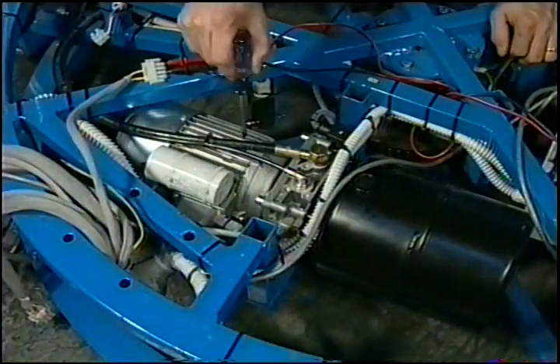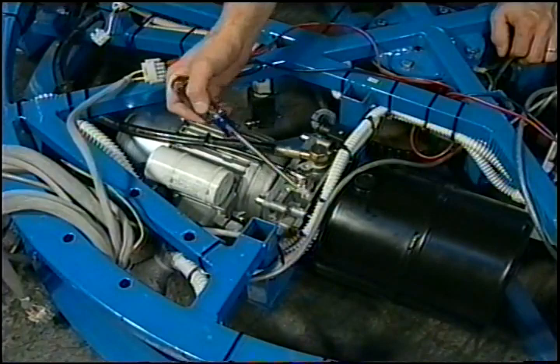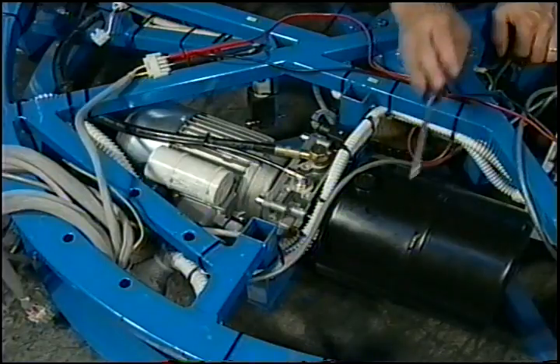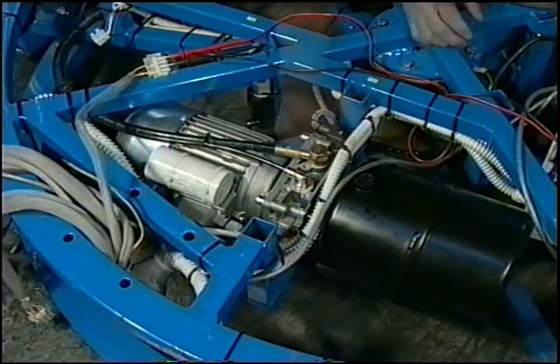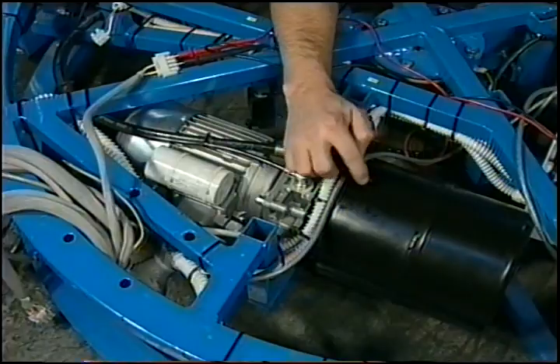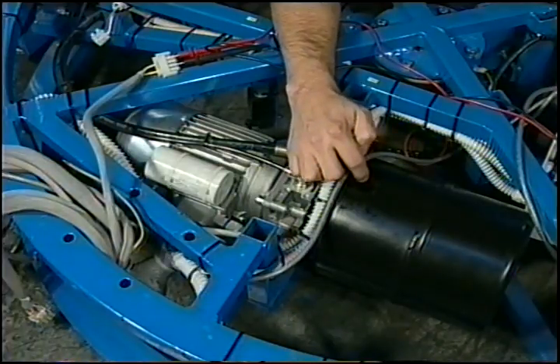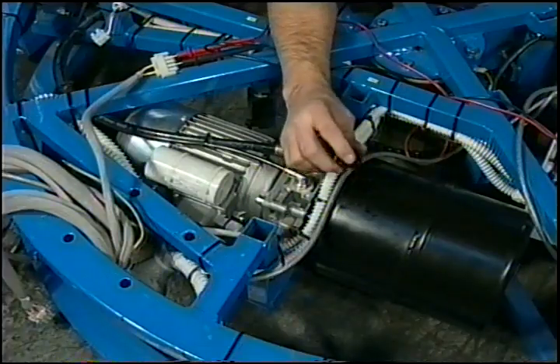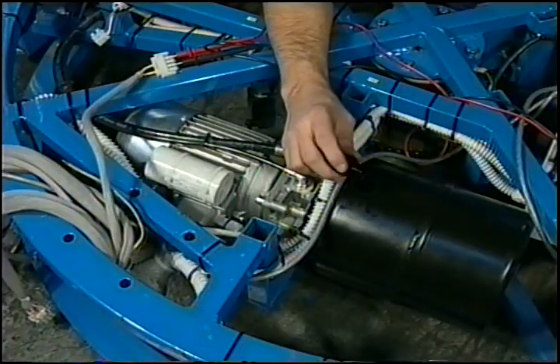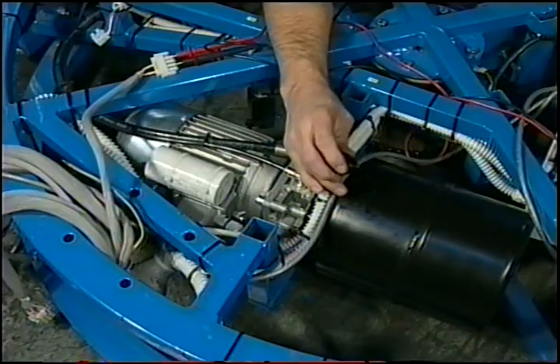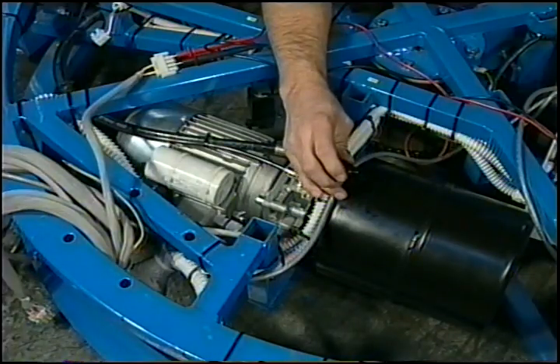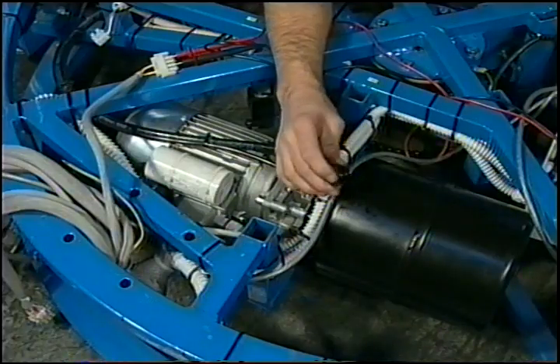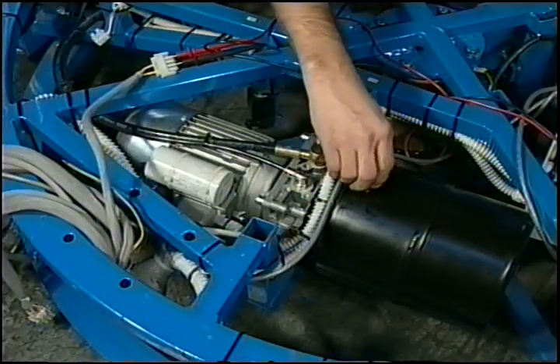This is your pump motor, and this is your pump manifold, and this is your reservoir, and inside the reservoir is where the pump is. When you fill this, you want to fill it about 1/2 inch from the top of the fill hole, and you want to only use a Mobil DTE 24 hydraulic oil, which crosses to a Grainger's 3KD 75. That's 3KD 75 at Grainger's.